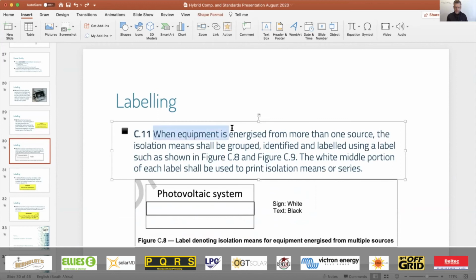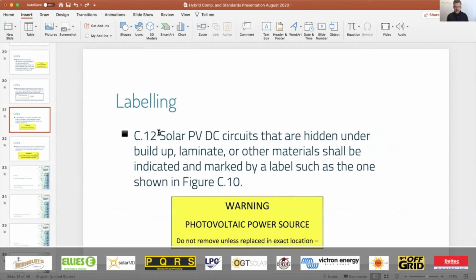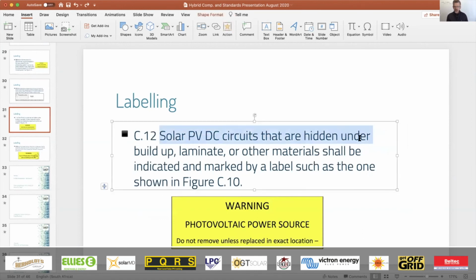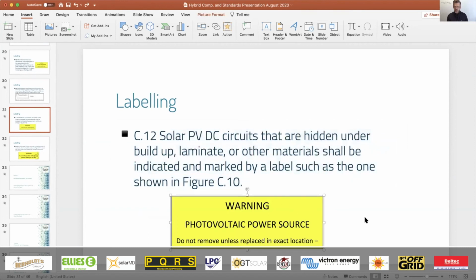Then it goes further to say, when equipment is energized from more than one source, the isolation means shall be grouped, identified, and labeled using a label such as shown in figure C8, which is what I've got at the bottom over here, where it says photovoltaic, that white label over there. And then it says the white middle portion of each label shall be used to print isolation means or series. Yeah, so that is interesting. The solar PV DC circuits that are hidden under buildup, laminate, or other materials shall be indicated and marked with this type of label we've got over here.